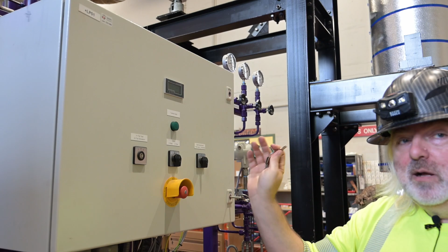Above the emergency stop, we have our speed adjustment, raise or decrease. We have our turbine stop, start. And again, to operate these switches, the main control panel needs to be in skid control. If the system is not in skid control, these switches do nothing.